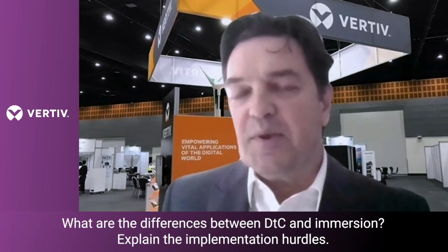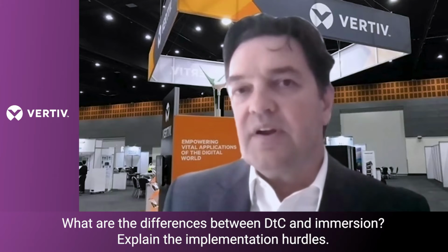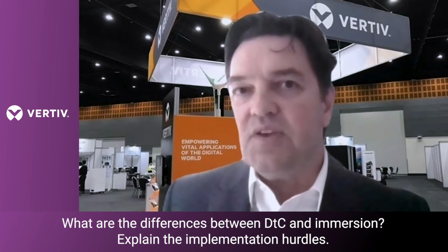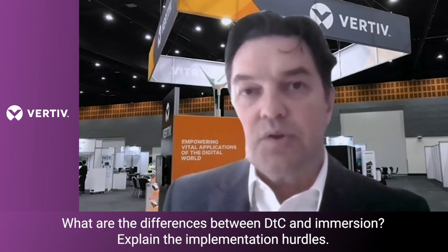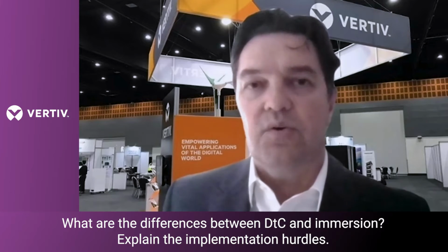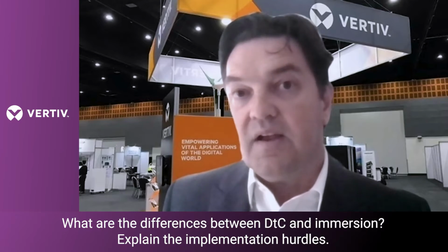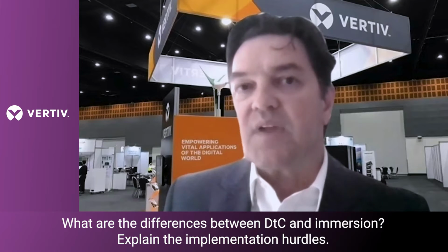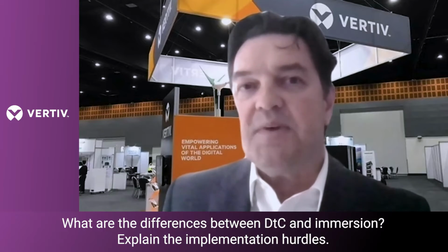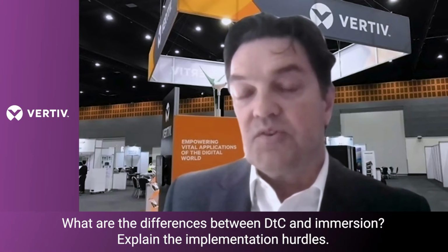And it's quite disruptive, because your technology spaces are typically already built out, and they've been designed to manage airflow. Now, to take liquid directly to the servers, you need to put in pipework and pumping infrastructure to support this. Not to mention any tanks, immersion chassis, or server racks that can accommodate liquid cooling. So we're specifically talking about pumping units and pipework, which means you need to take an existing data center offline for some time to be able to do that.